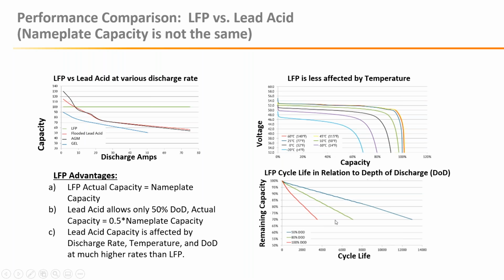A word of caution to everybody. There are some battery manufacturers out there that say they can reach up to 10,000, 12,000, 14,000 cycle lives. I always tell people to be aware that although it's a great thing to say, 12,000 cycle lives, you have to be careful what they're telling you. Is this assuming a 50% depth of discharge? Is this taking into account temperature? Is this taking into account the different charging and discharging parameters and the project itself? So just be wary, or at least be cautious, when you are choosing a battery, that the cycle life is not only protected by the warranty, but also takes into account a realistic project.